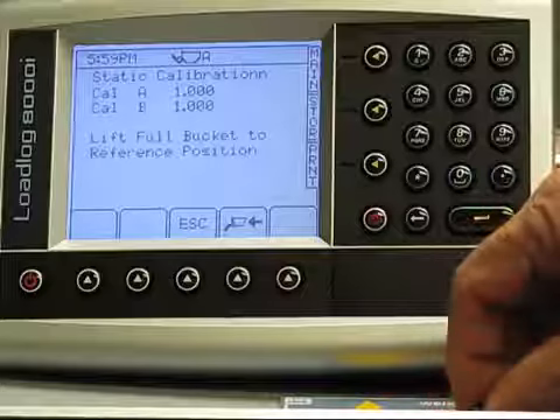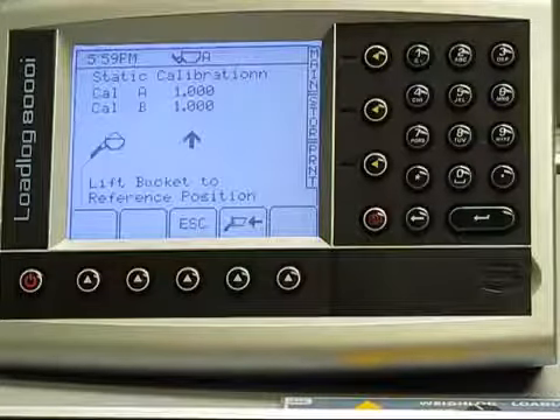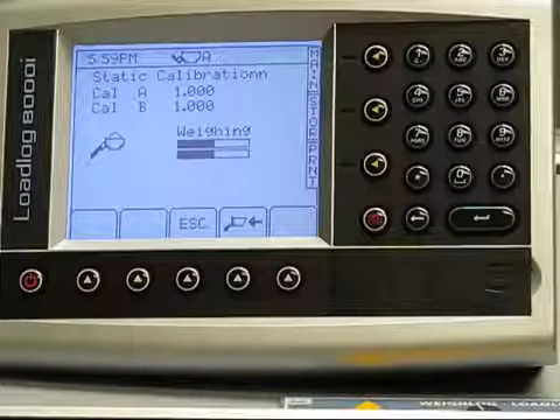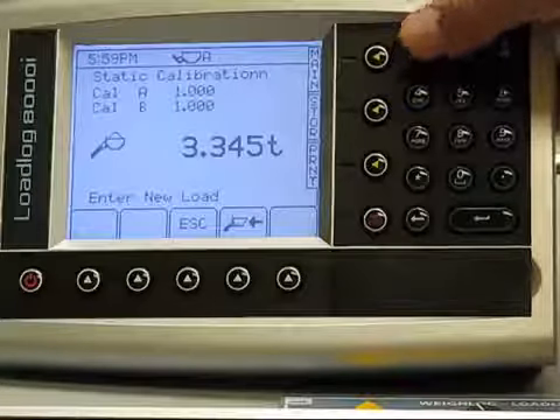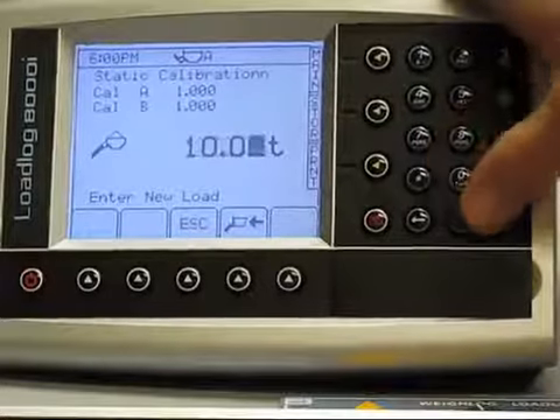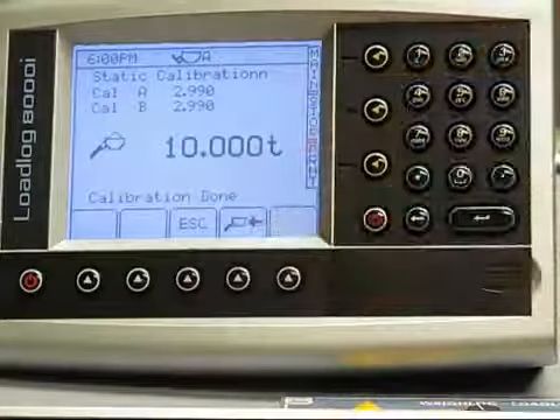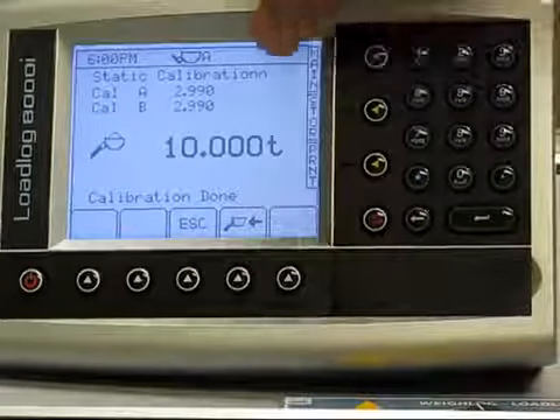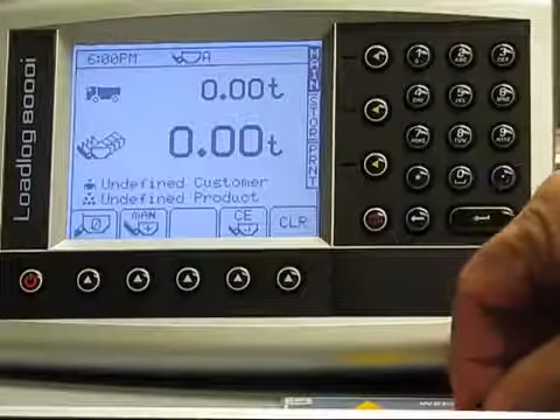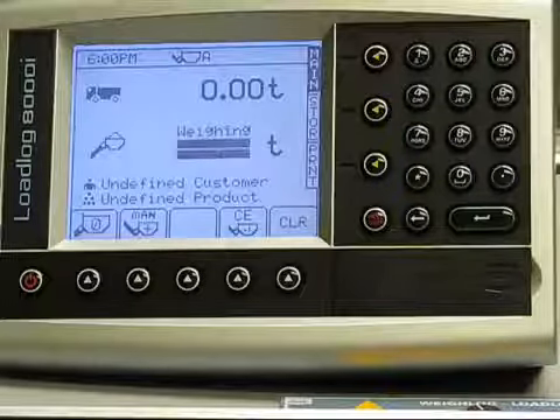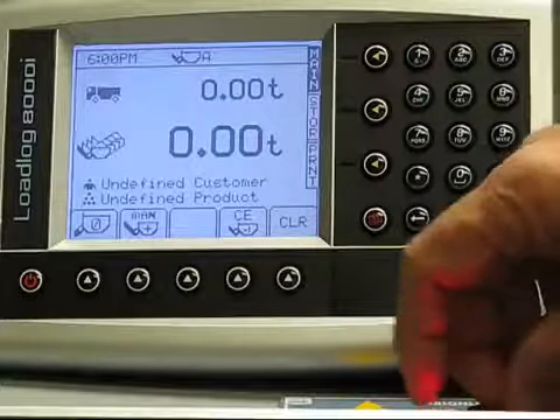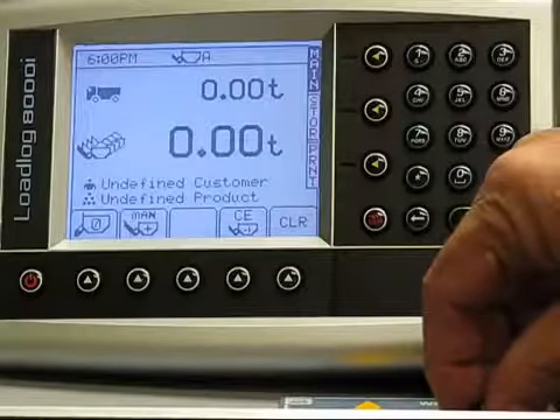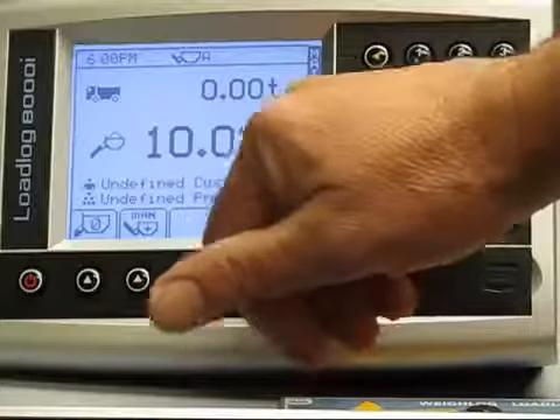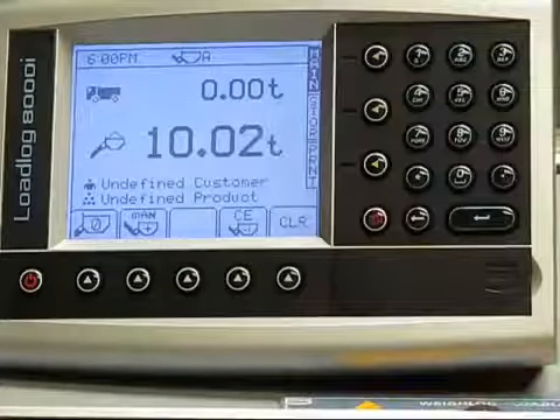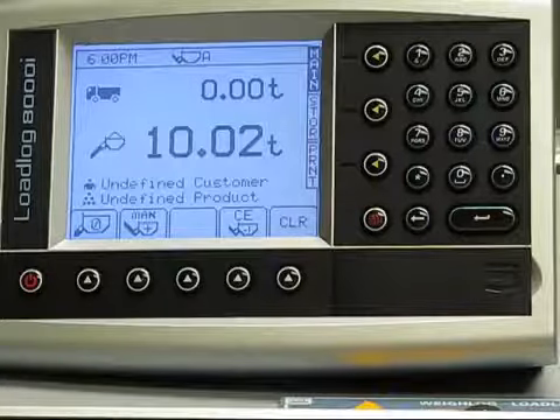the keyboard, and you can see that it readjusted our cal numbers, and it's asking us to lift to the static position. It will weigh again, and when it weighs, it will display the weight, again 3.345 tons. We're just going to simply tell it that that's 10 ton. Notice that it's told us that the calibration is completed. If we press the button in the upper right hand corner to the main screen and we lift the bucket, because we've told it it's 10 ton, it should weigh 10 ton, which it does. It should also weigh 10 ton in dynamic, and in this case it's 10.02, which would be 40 pounds within, certainly within reason of 10 ton.